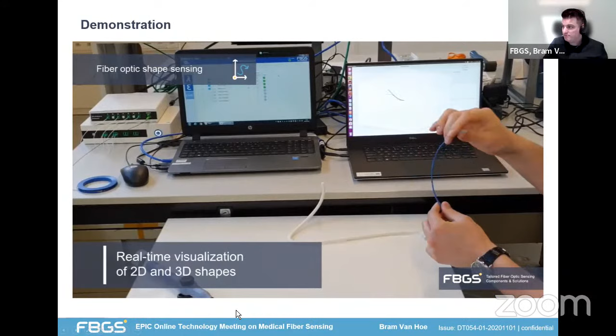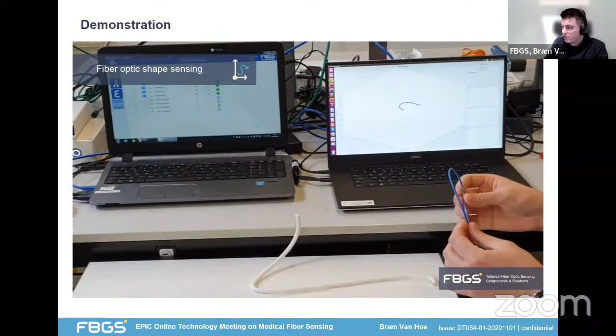I'll show you a small movie just to show you the technology. Maybe you've seen this movie before. We have here an optical multicore fiber, which is inserted into a catheter. We see here on the left a measurement device with a separate fan out in this case. So this is still a modular setup where the measurement device is separate from the fan out. So the multicore fiber is inserted here, and then the individual fiber cores are connected to an interrogator. And the shape is visualized here on the right, and you see that the real-time shape is actually tracked in 3 dimensions. And in this case, I think the length was between 20 and 30 centimeters of the tracked piece of fiber.